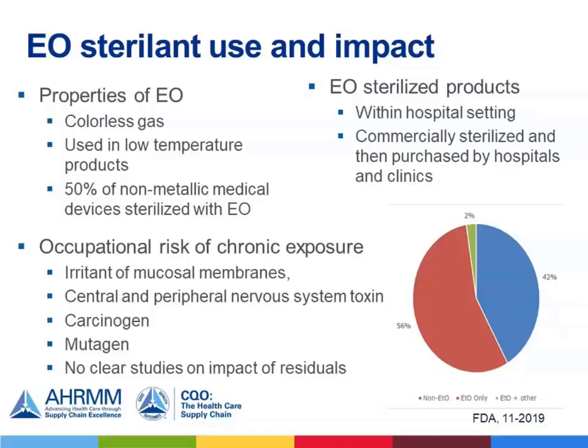And then the final thing, and this is something we'll talk about more later, is that when we sterilize something with ethylene oxide, there is a residual amount of ethylene oxide that sits on the thing that we sterilized. And when that package gets opened, either the patient or the healthcare worker is exposed to a risk of this residual. We have data on residuals, but we don't have any data that tells us what that means. So if a healthcare worker is opening these packages over and over and over, or a patient is using something that has been sterilized by ethylene oxide, what is the impact on a person there? And we don't know that information. Next slide.